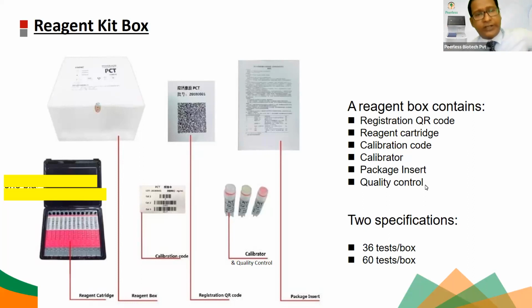So what the manufacturer is doing is first providing a calibration code. Once you scan it with a barcode, we provide the barcode along with the instrument, it takes the calibration curve inside. But now you do not know whether the factory calibration curve which is provided is correct or not, right? Because it's the initial calibration curve, prepared while the kit was manufactured. Sometimes in transit something may have happened, and things may not be 100% fine. So we need to validate the calibration curve.